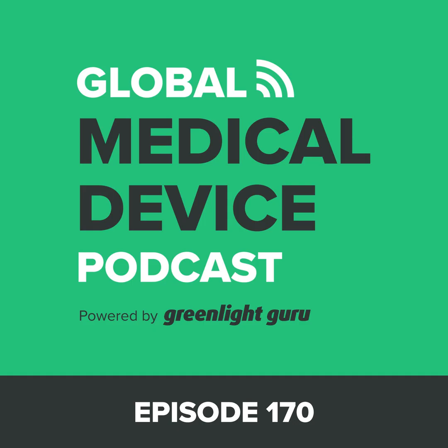I think another good thing to include would be user interface screenshots. I think this is another piece where a lot of companies are very early stage. Maybe they have a smart algorithm that can do something that no one else can do, but they haven't quite built the front end. And FDA is going to want to see it. They want to see what it looks like to those patients, what it looks like to those physicians, what your device output will be.